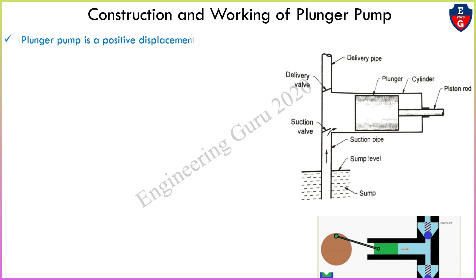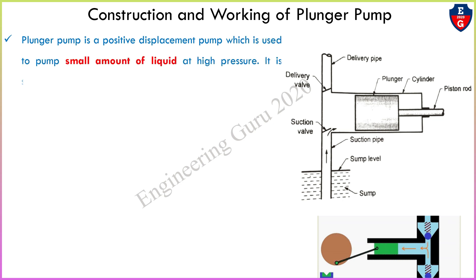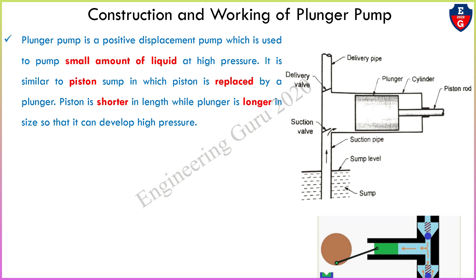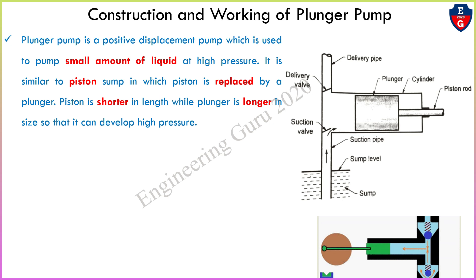Now understand the construction and working of the plunger pump. A plunger pump is a positive displacement pump which is used to pump a small amount of liquid at high pressure. It is similar to a piston pump in which the piston is replaced by a plunger. The piston is shorter in length while the plunger is longer in size, so that it can develop high pressure.